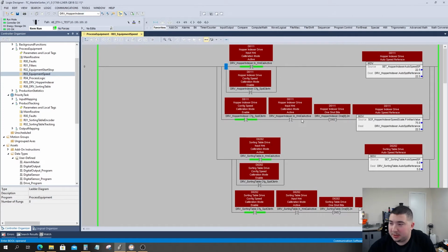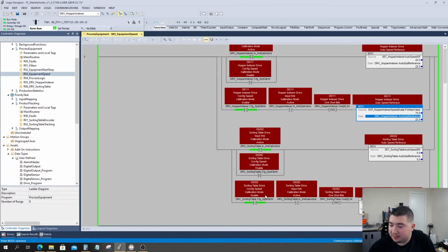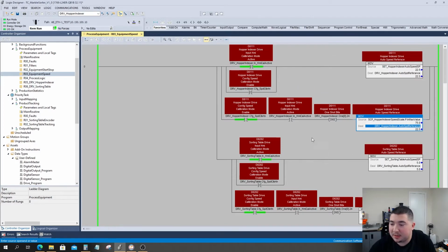So the first thing we need to do is tell the system what speed we want to run at during the calibration mode. Now, because of the size and the weight of the equipment, it's really easy for the system to go at full speed. So what I've done to make the computation easier is just send the maximum output to the device itself. In this case, for the indexer, our max speed is 75, and that's in RPM. So when we're doing the calibration mode, we'll change our output speed to the full speed, which is 75. Same thing for the sorting table, but its max speed is 45, so we'll tell the drive to go to 45, and we'll then monitor its speed from the input.